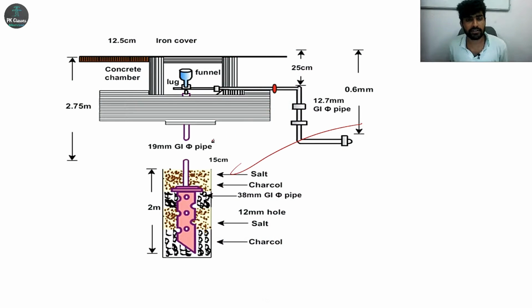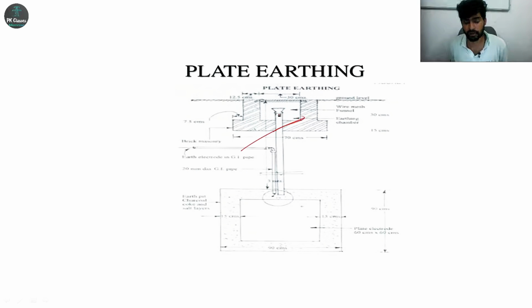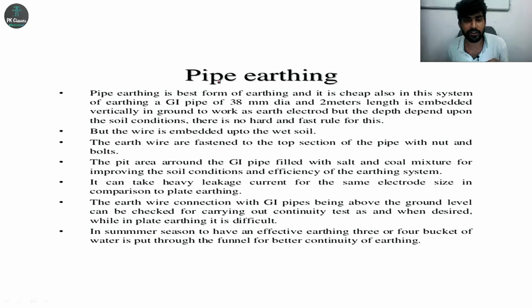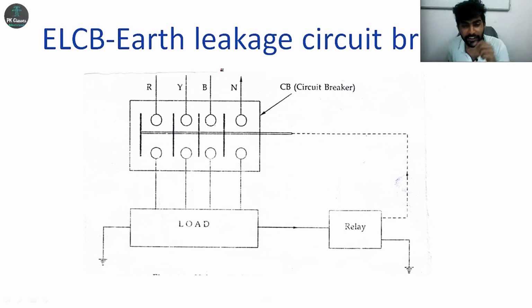You can draw this diagram also, plate earthing and then pipe earthing diagrams. If you want, you can copy this pipe earthing, and for plate earthing similarity will be there, only dimension is different, 80% is same working and placing everything, okay. Next we'll see earth leakage circuit breaker. Circuit breaker which breaks the circuit when fault occurs or over current occurs, over voltage occurs, right? Earth leakage will be there if there is any leakage in the load, for example domestic appliances or electrical equipment, so the earth leakage circuit breaker will operate, right?